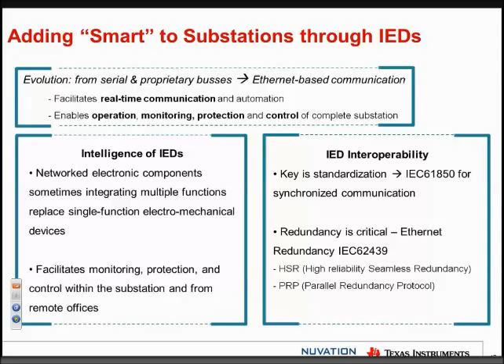As we look at the IEDs, with more sensor integration, we have more data input, which ultimately means increased measurement. This is also challenging as power equipment becomes more complex with steady, non-predictable energy sources. This requires more analytics and control, which gets more complex with more IEDs in the substation automation system. The other piece is communication, supporting legacy serial-based or proprietary communication, as well as Ethernet-based platforms.